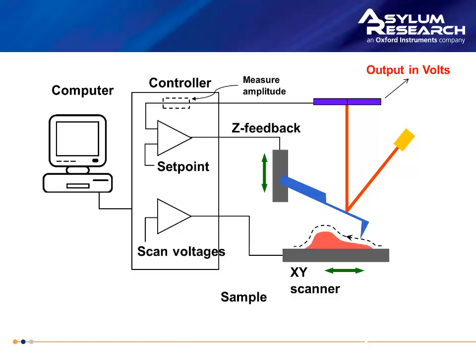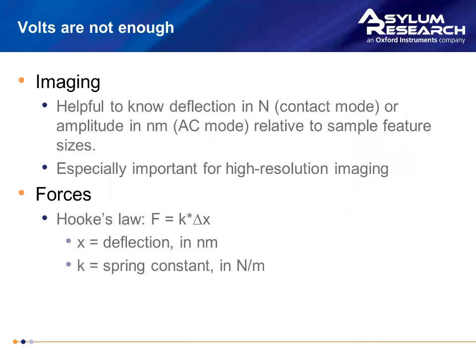AFMs measure the deflection of a tip by monitoring the position of a reflected laser spot on a segmented photodetector. Because of that, the actual measured quantity coming out of the AFM is a voltage which corresponds to the position of the laser and, by extension, the deflection of the cantilever. The thing is that for a lot of measurements we're interested in, having our data in terms of volts just really isn't enough. For imaging, for example, and especially for high-resolution imaging, we really need to know the deflection for contact mode or the amplitude for AC mode in terms of newtons or nanometers, not volts.